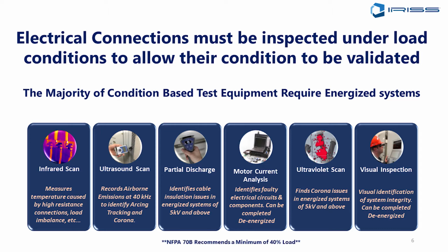Partial discharge testing is a little different. So when I talk about arcing, tracking, and corona, those are all partial discharges, but those are partial discharges directly into air, right? From the conductor material that's making noise directly into the air, and it transmits therefore quite readily through that medium.